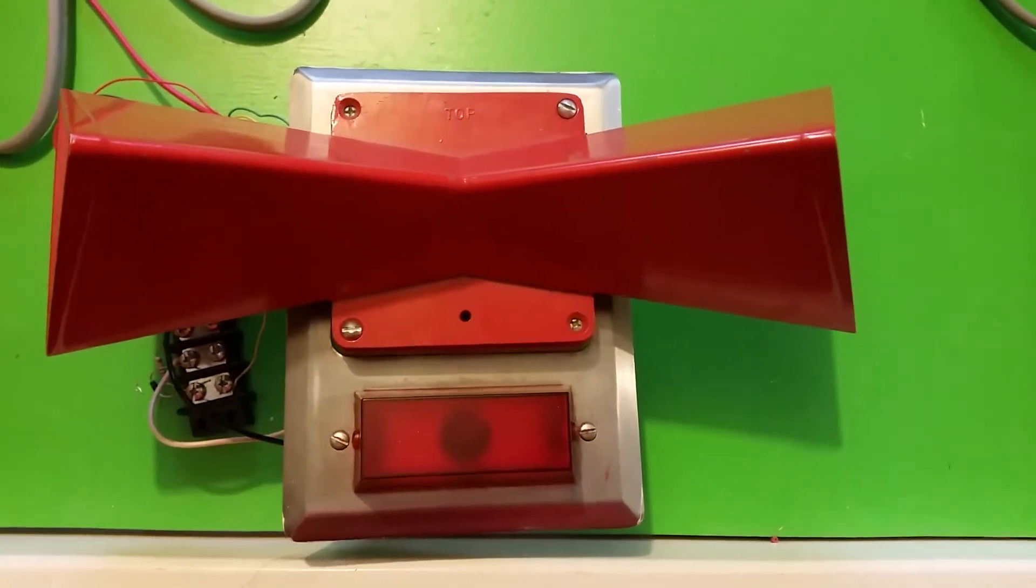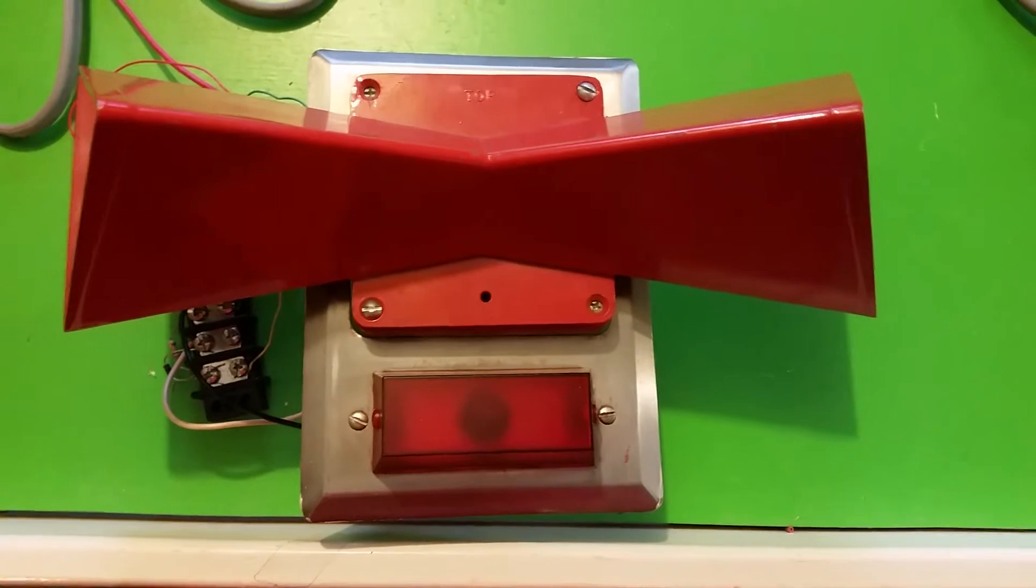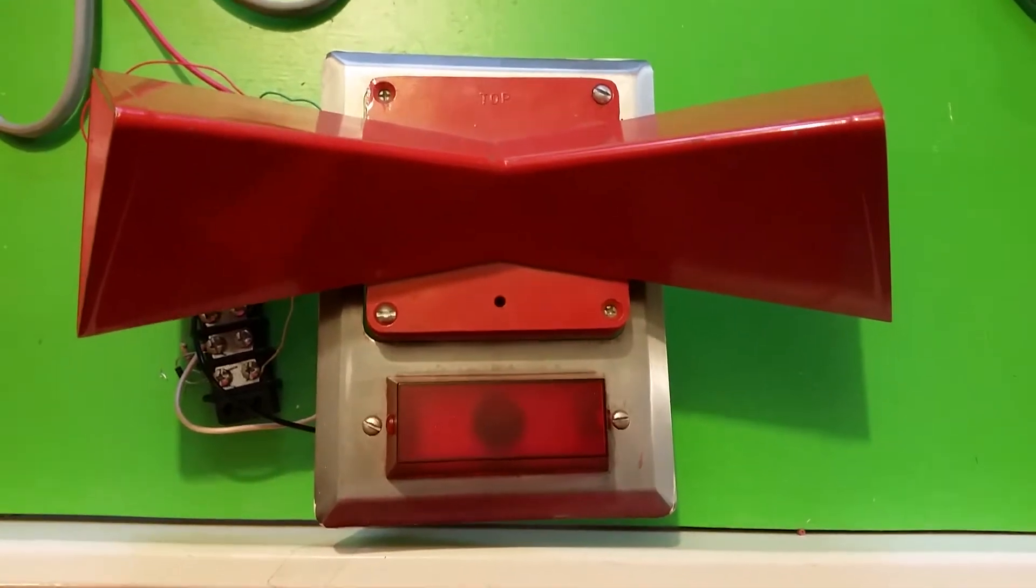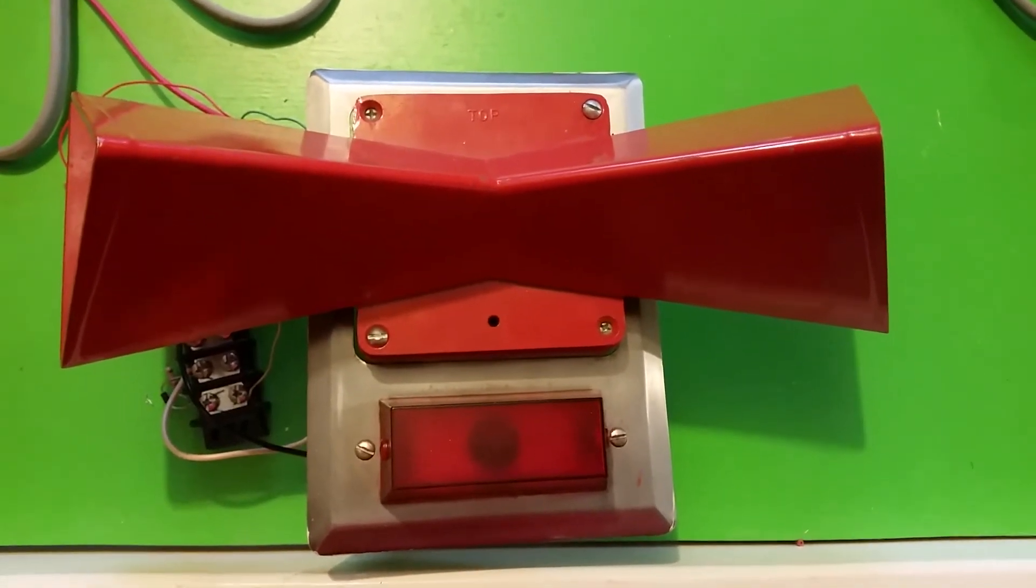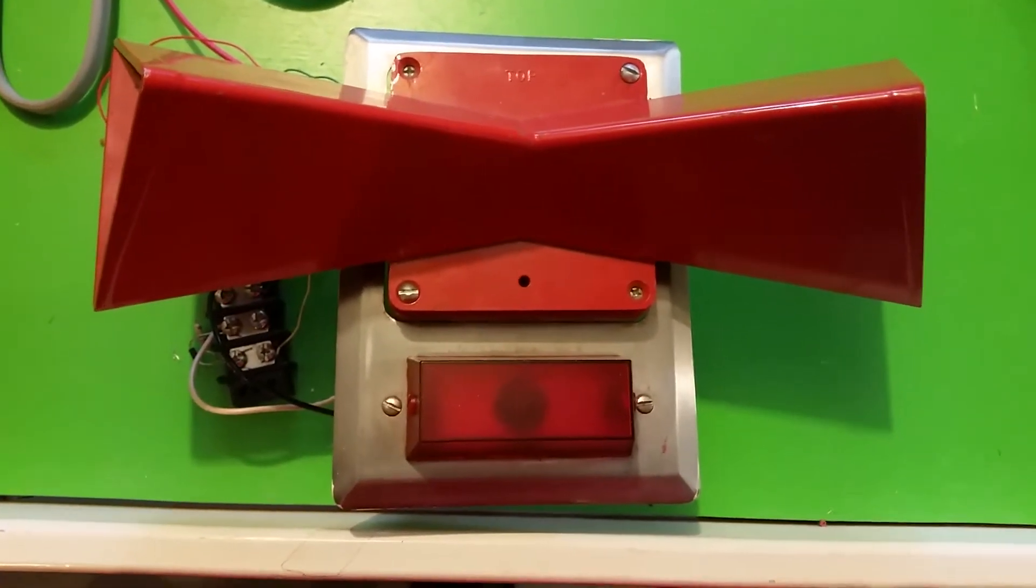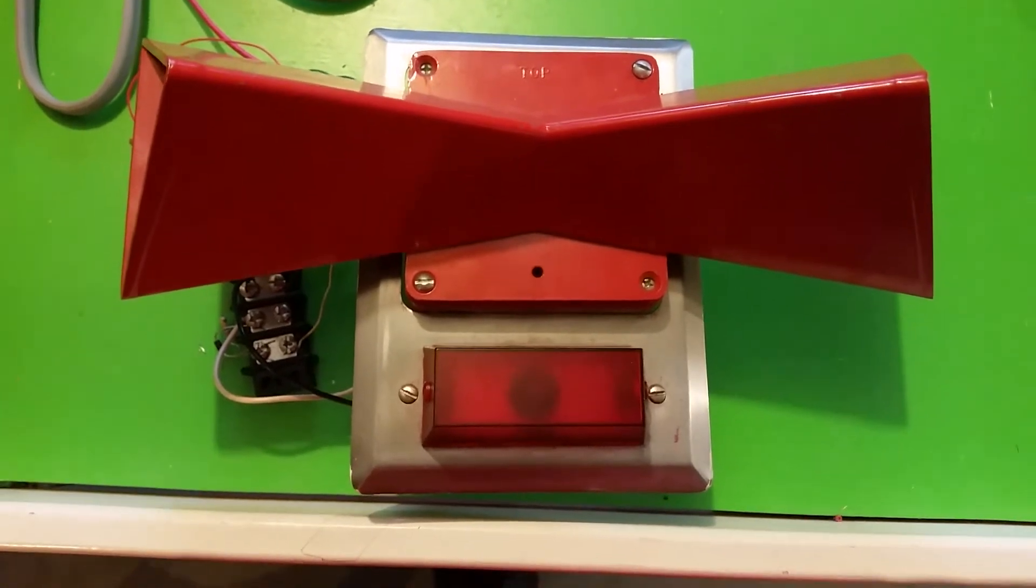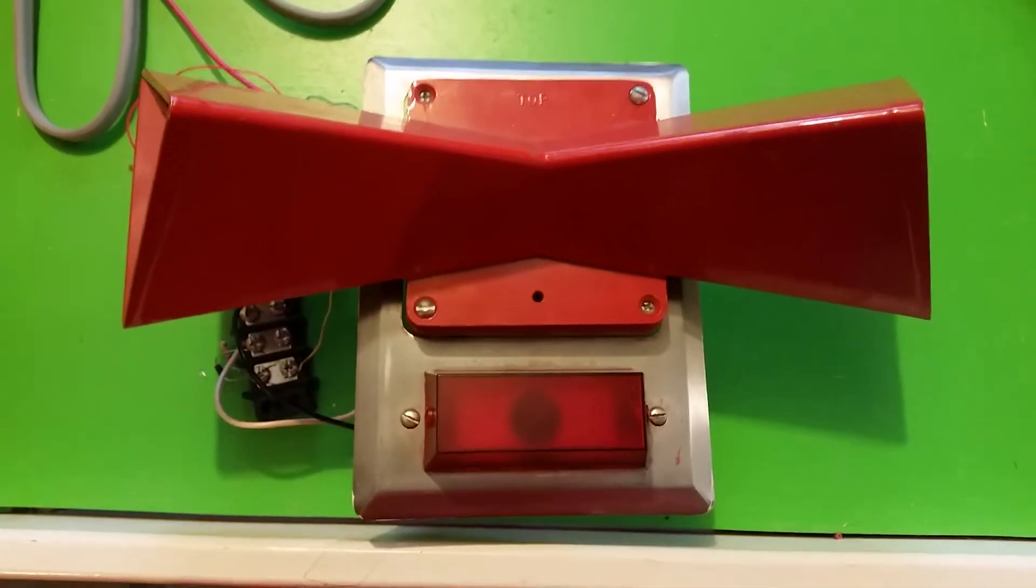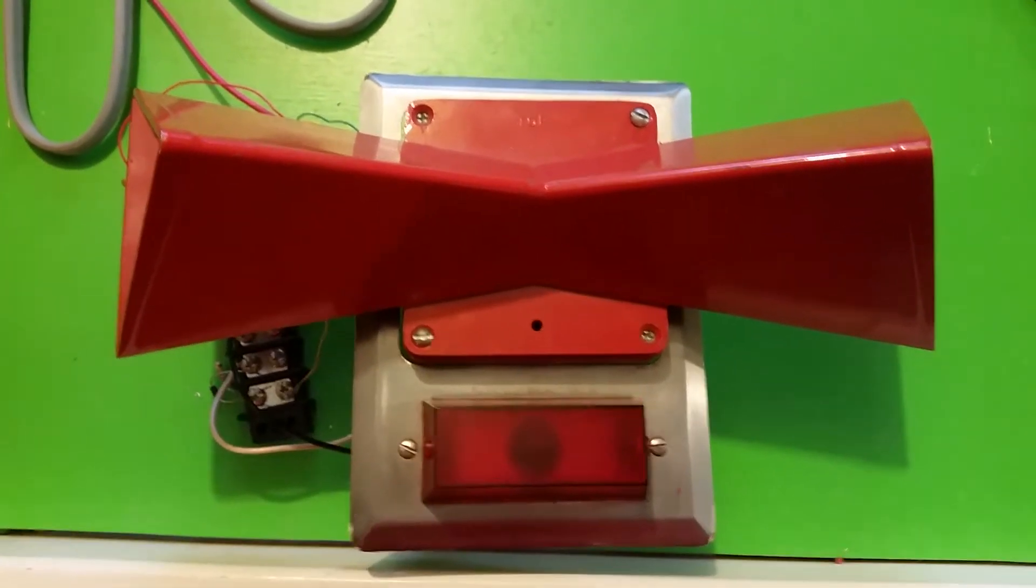Now some of you may know this. With the 4050 series light plates, they are not diode polarized. So you need a diode to polarize the circuit for proper supervision. I'll explain why.